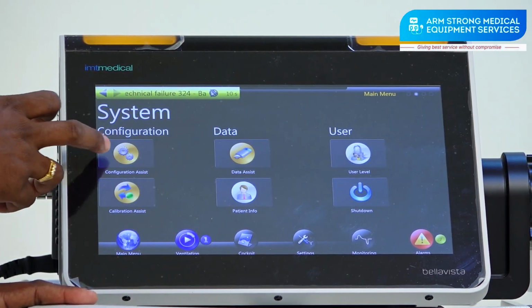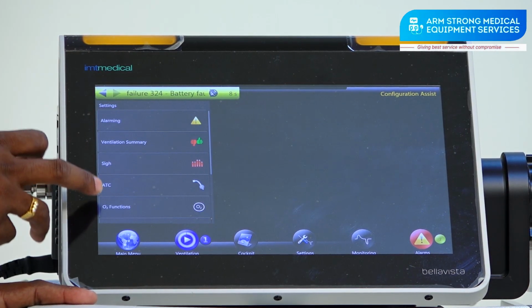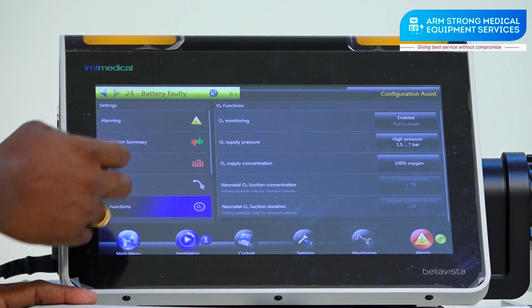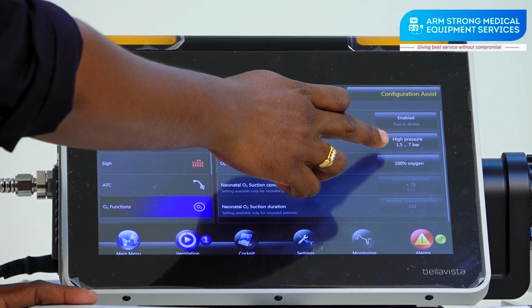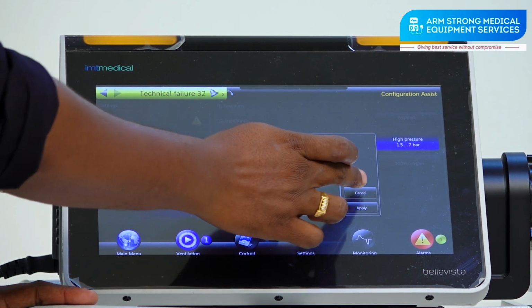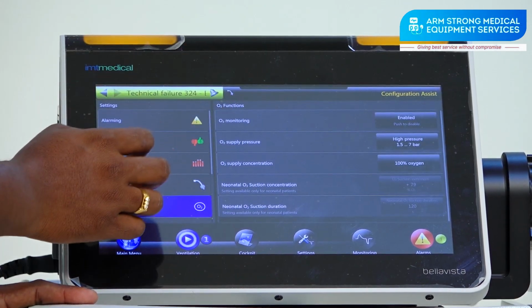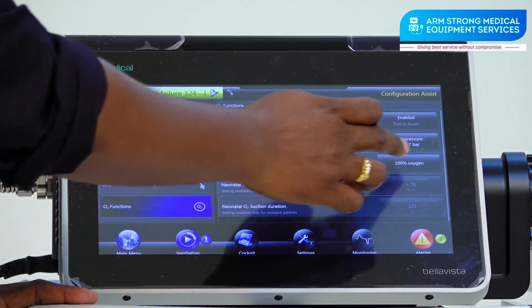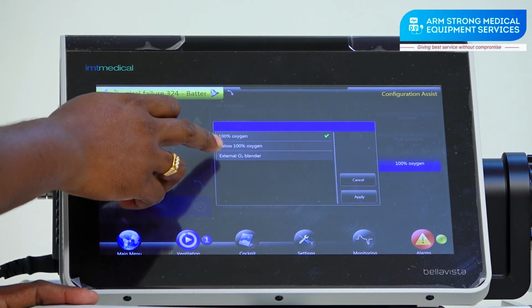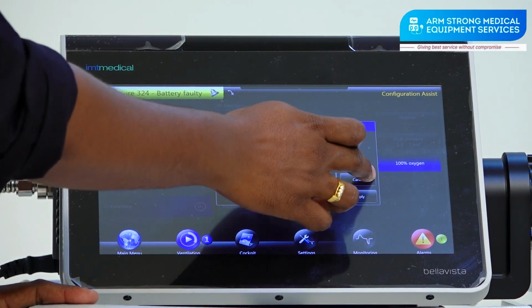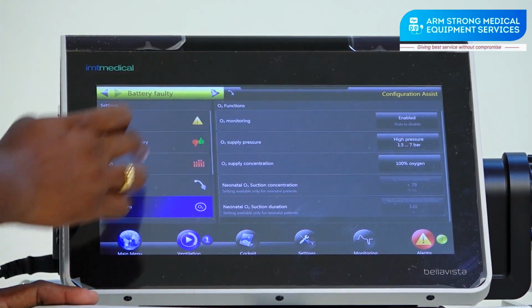And this is the first page, this is the second page, configuration. Previously I told about the O2 functionality. We have a low pressure also. This is high pressure. If you want to use with a flow meter, you can select the low pressure also. So this is the data about the O2 functions. O2 supply concentration also we have below 100%, and the external O2 blender, if you are using that, you can choose that also.